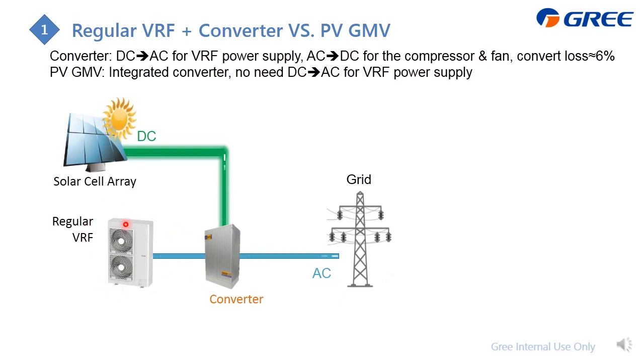This is, for example, the regular VRF, and this is the converter. It's handling the power, either from AC, from the grid power supply, or from DC, from the PV panels. So for this case, the converter needs to, if it gets power from DC, convert this DC to AC, then power the regular VRF. And for the compressors and fans inside, if they are DC, which is very popular, they need to convert this AC back to DC again, to drive the inside compressor and fans. So the total conversion loss there is 6%, for two conversions.